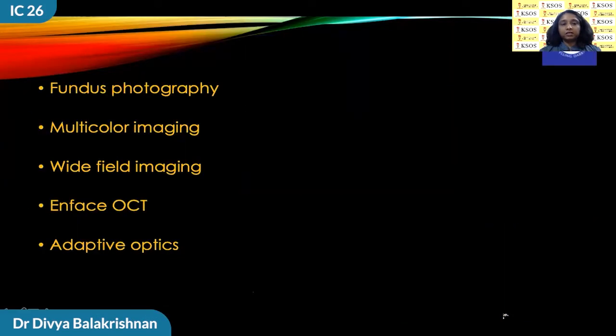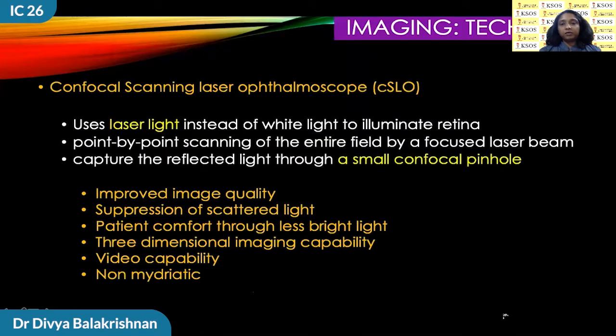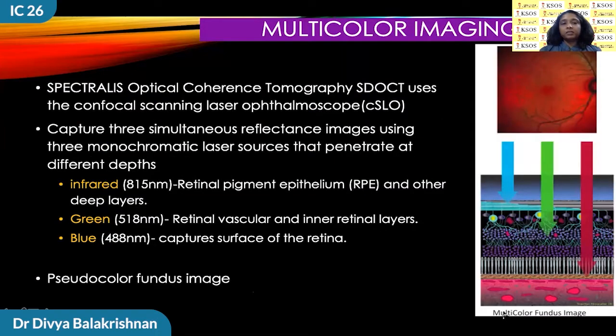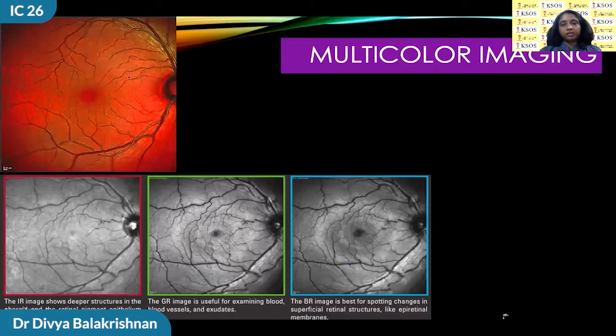Imaging techniques have evolved with time, and confocal scanning laser ophthalmoscope is one of the techniques being widely used in recent imaging systems. It uses laser light instead of white light to illuminate the fundus, point by point scanning of the entire field by a focused laser beam, and captures the reflected light through a small confocal pinhole. Multicolor imaging is one option available with the Spectralis. It uses three different laser beams to create a pseudocolor image of the fundus. The IR reflectance image shows deeper structures in the choroid and RPE, the green reflectance image is useful for examining blood vessels and exudates, and the blue reflectance image is best for spotting changes in superficial retinal structures like epiretinal membranes.